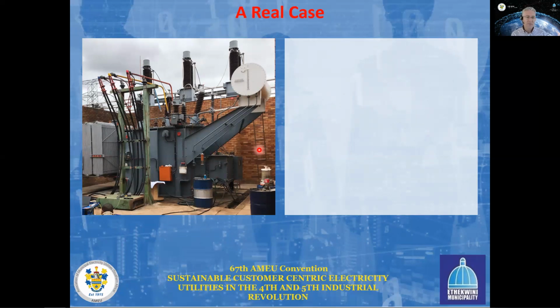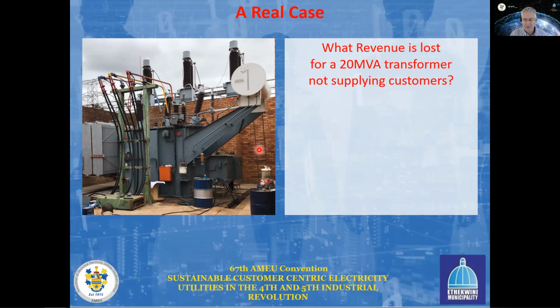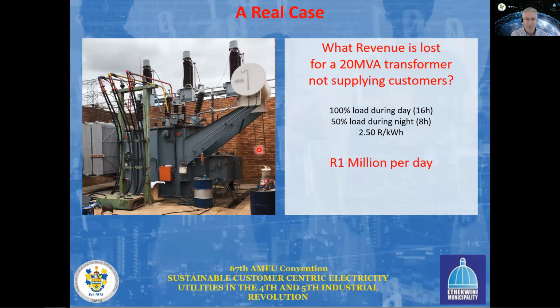We were then called in to assist and to also showcase our test equipment. And when I stood there at the transformer, I said, this is crazy. How can this be? A transformer like this not supplying customers? The question that popped up in my mind was, what revenue is lost for such a 20 MVA transformer not supplying customers? I took some assumptions. I said, well, let's say this transformer is loaded 100% during the day, that means for 16 hours a day. It is loaded 50% during nighttime. And let's assume a rough R2.50 per kilowatt hour, just because it makes the numbers easy. The revenue that is lost for this transformer not supplying its customers to the municipality is 1 million rand per day. 1 million rand per day, easily calculated by using this formula, as you can see down here.